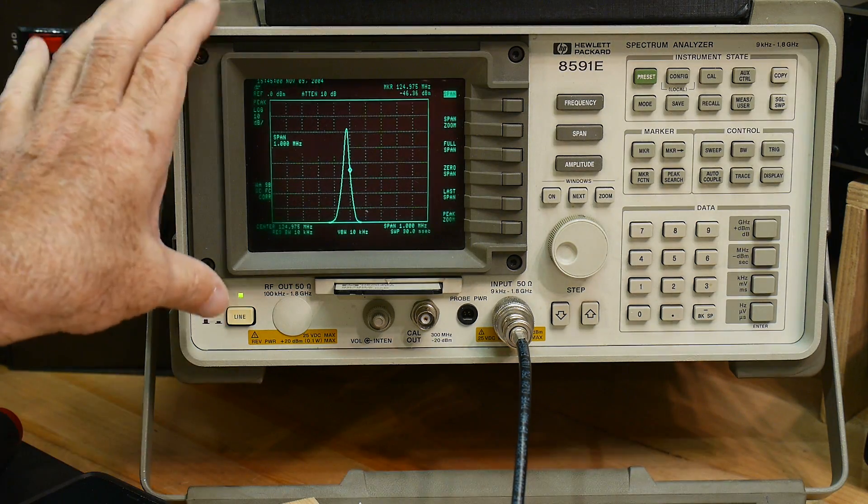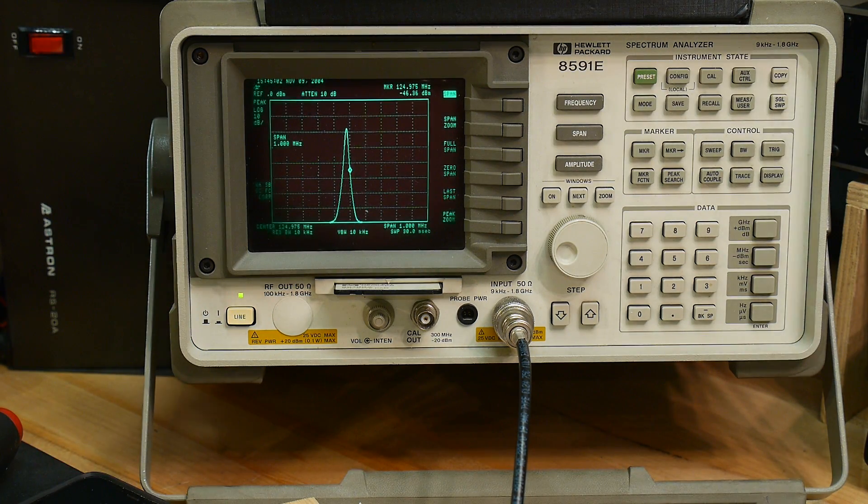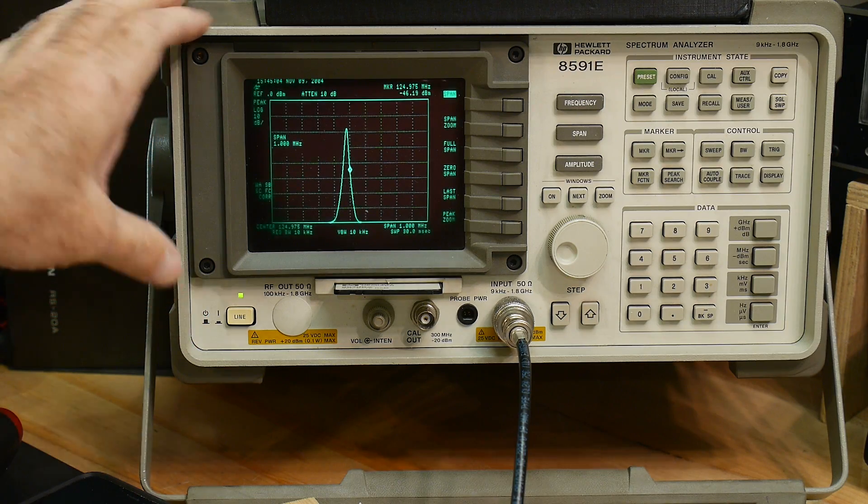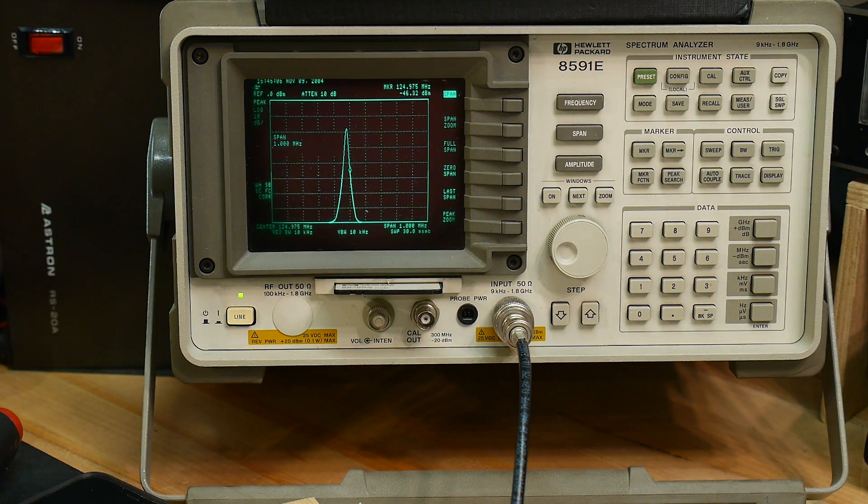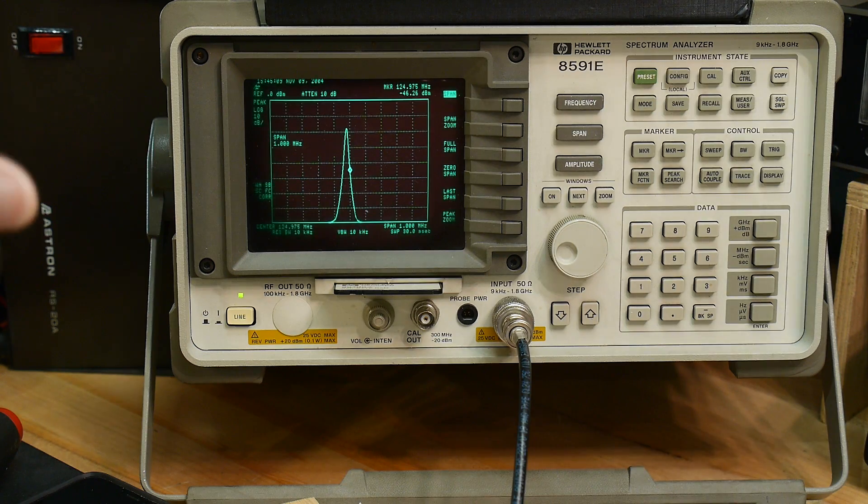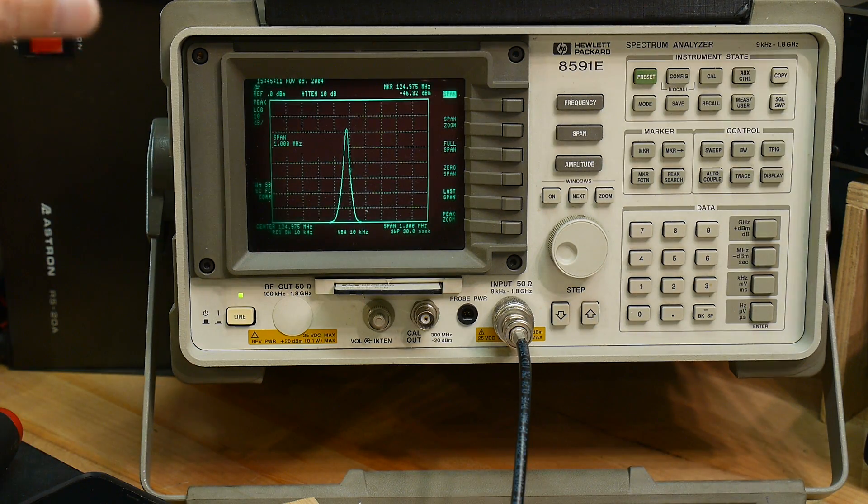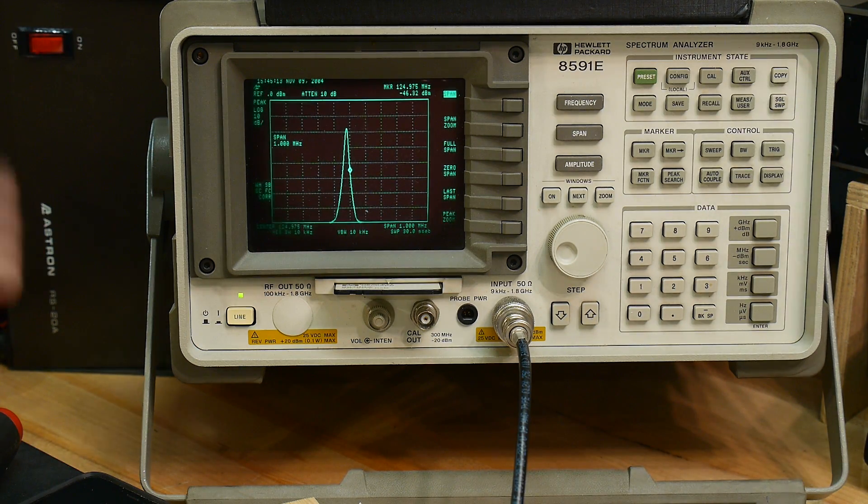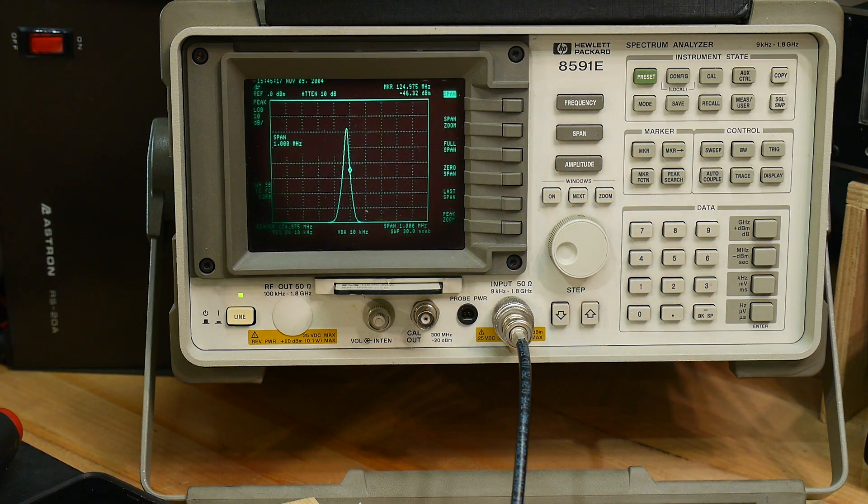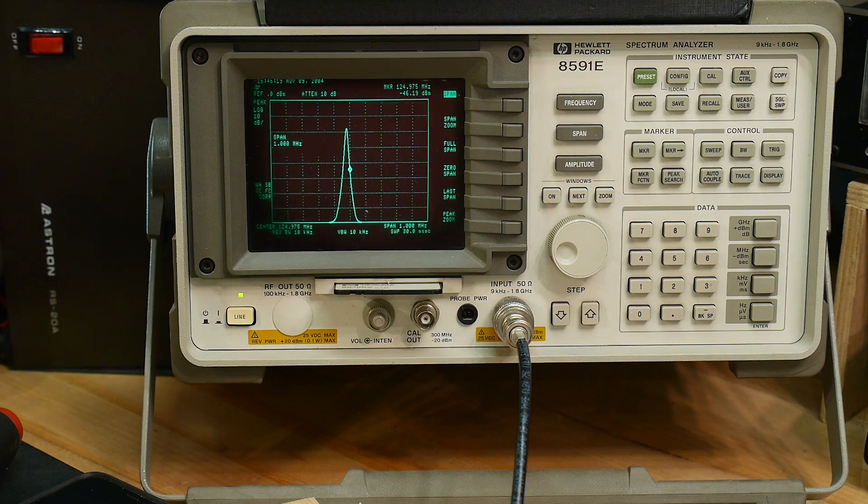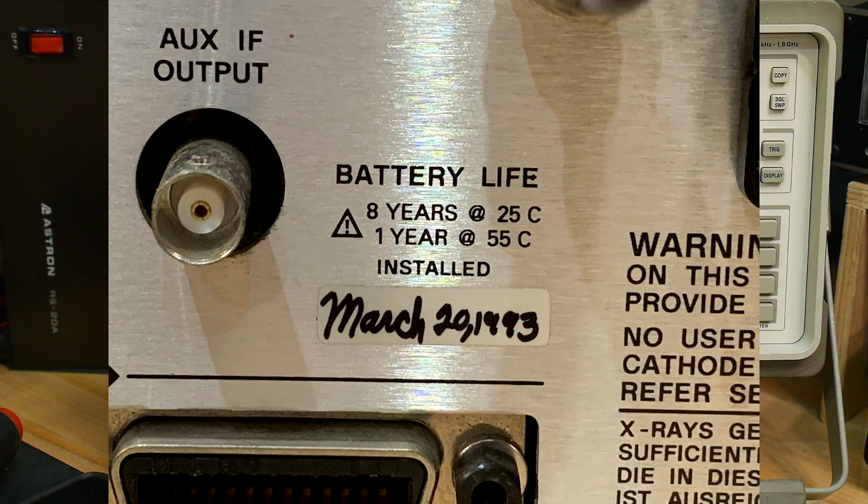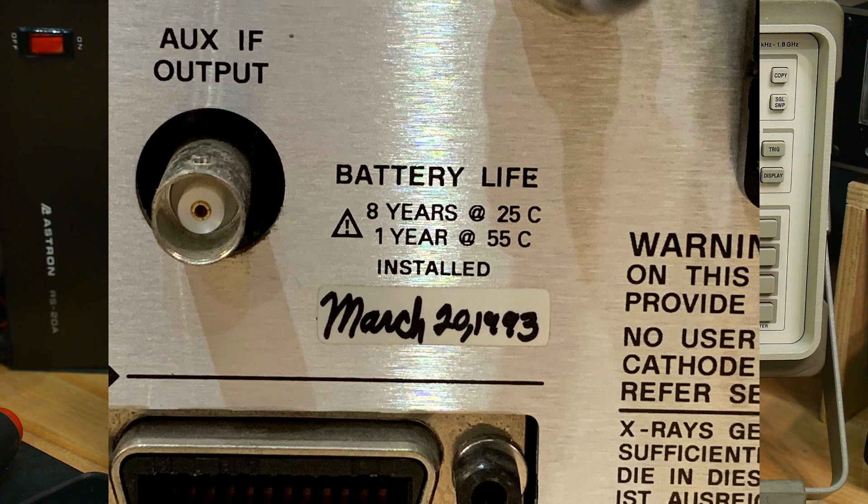I decided to replace the battery in my spectrum analyzer that backs up the RAM and the calibration data. There's a lithium cell in there, not rechargeable, but a lifetime battery. This is supposed to be good for eight years, so I figured mine's probably due. On the back of the instrument is written when the battery was replaced, and it was put in March 20th of 1993, so I think it's exceeded its eight-year life, so time to do it.